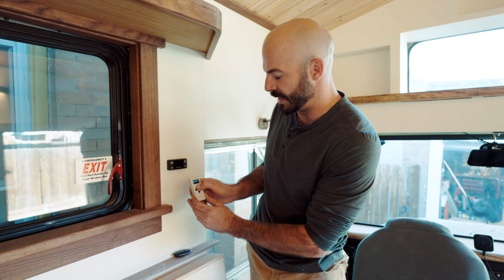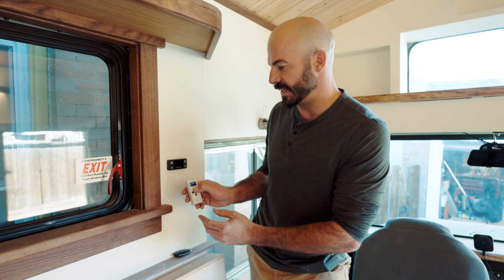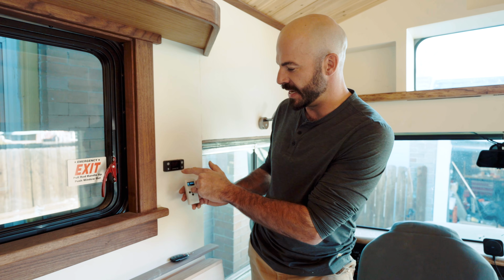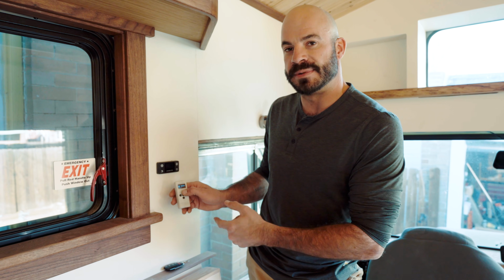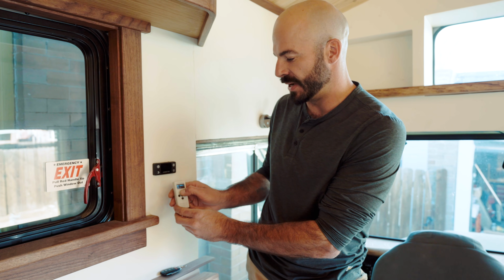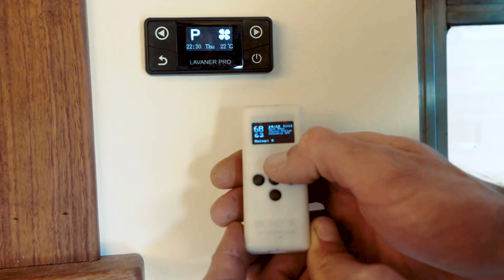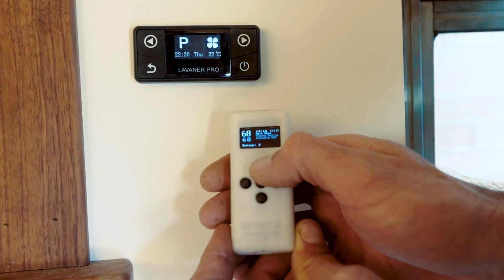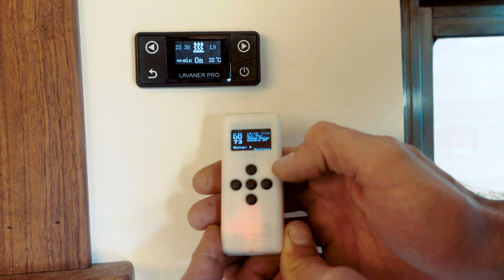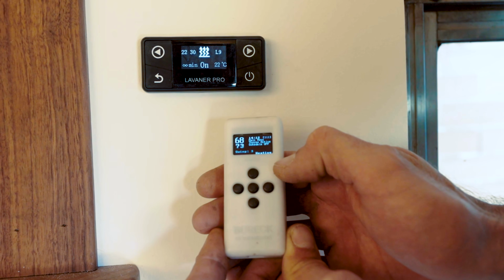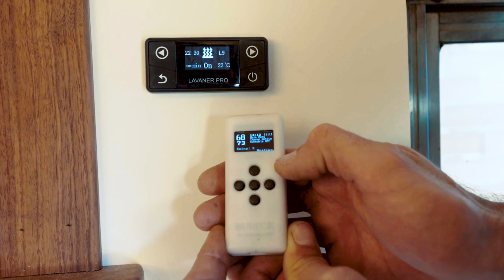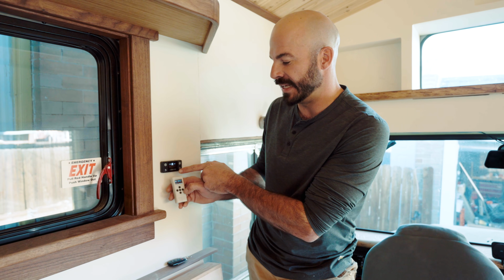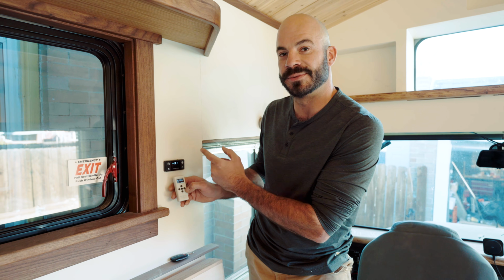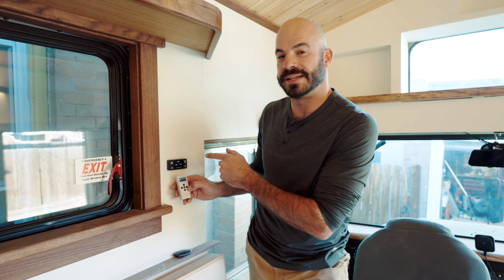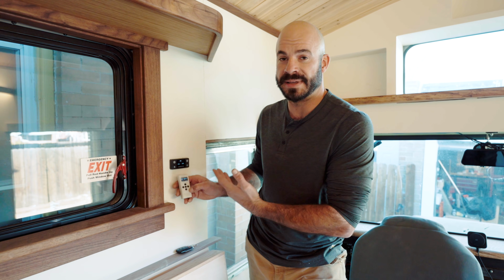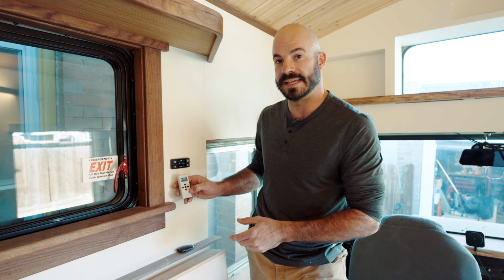So I'm going to go ahead and turn it up right now. It's 68 degrees in here. And if you watch this screen and this screen, you'll see what happens as I turn this up. So I'm going to go ahead and turn this up. And once we get past our set point, you're going to see a red light flash here. See that red light? And then our diesel heater just turned on. Now it will stay on until it hits our set point, at which point it will then signal our diesel heater to turn off, and it'll do that maintaining the preset temperature that you have.